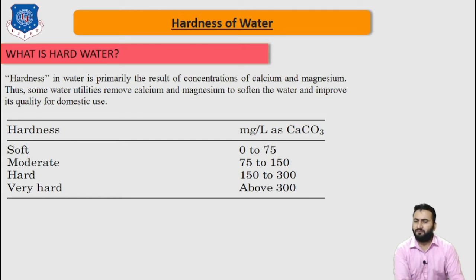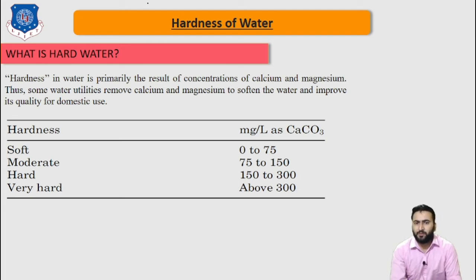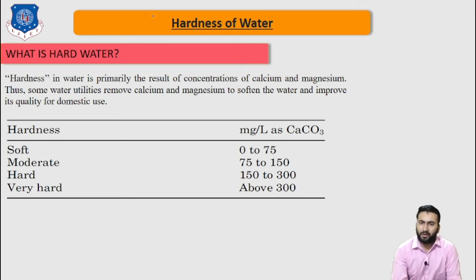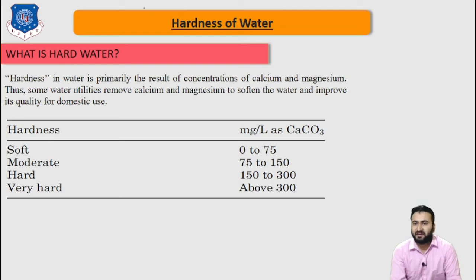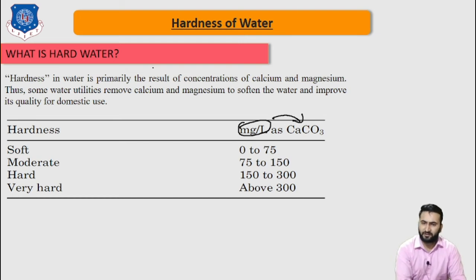Now let us discuss about the hardness of water. Hardness in water is primarily the result of the concentration of calcium and magnesium. Many water utilities remove calcium and magnesium to soften the water and improve its quality for domestic use. Other ions that produce hardness include iron, manganese, zinc, and aluminum, but these are generally not present in significant quantities. Therefore, total hardness is usually defined as the sum of magnesium and calcium hardness in milligrams per litre, measured in the form of CaCO₃.